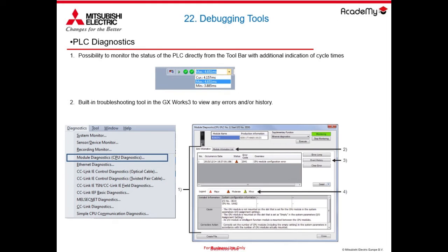For example, the diagnostic of the CPU of an R08 is telling us a bit about what the error code is, the current state of the CPU, and a description of the current error. Therefore, what the causes may be, what the corrective action may be, and the point at which it was identified. The error can therefore be jumped to: I deal with software errors mainly with jump errors, and GX takes us back to the exact point where the error is identified.